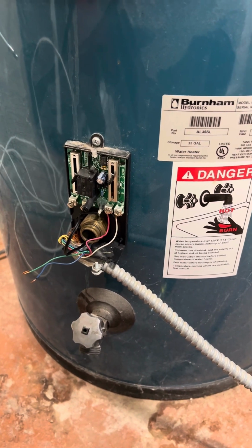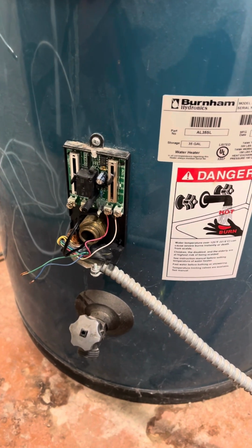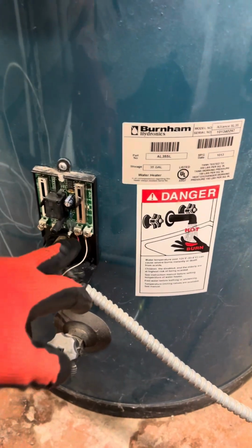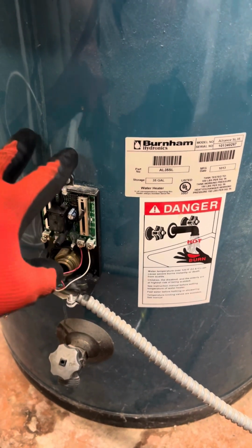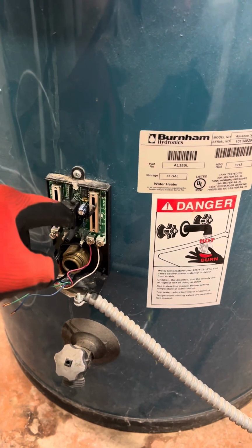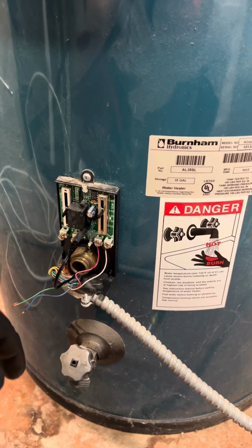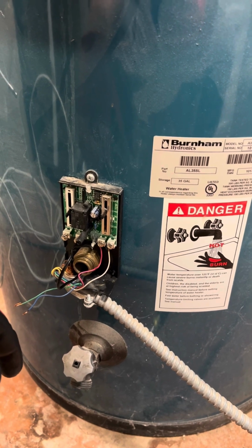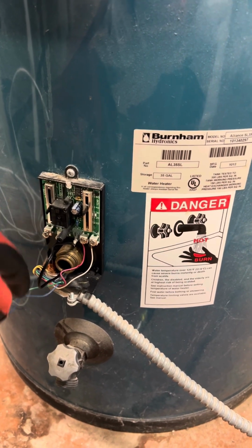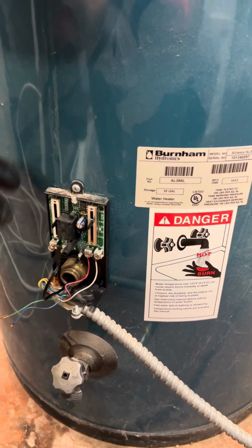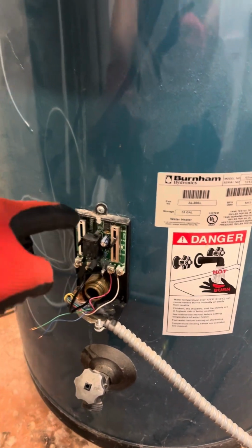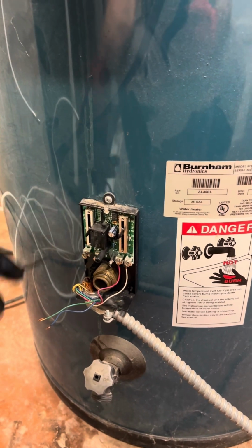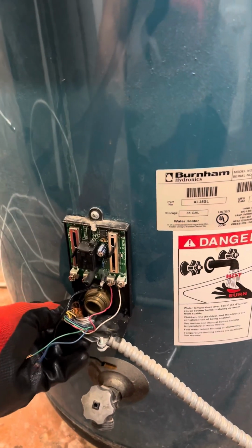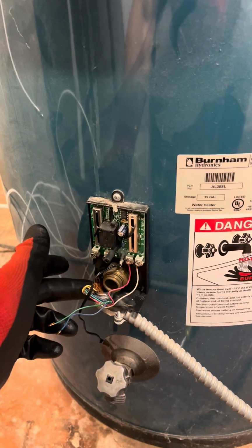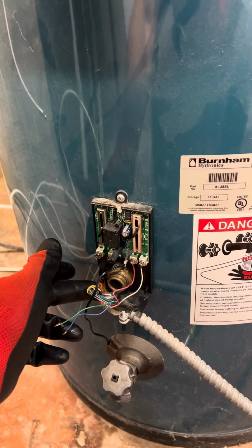All right. So we have the power off right now because nothing's happening with this module. So we have 24 here. Like I said, it's 24 present. That's supposed to power this up. It's not powering it up. So something is messed up with the little computer board. And like I said, once it needs water, it connects these two, and it will get it. So when I take this out, all it is, is one screw here. Take this out. This thing really just pulls right out. So we'll just take this out of the knockout, put a new one in, rewire it, and I'll show you how it's done.